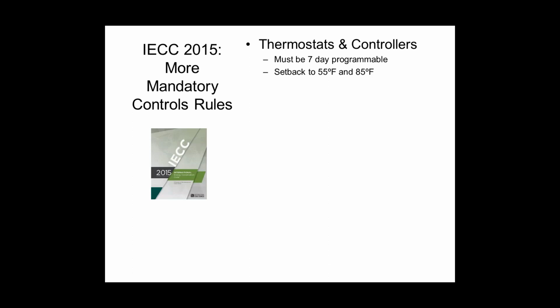You have to have the ability to set it back to 55 and 85 degrees. If the occupant chooses to change that later, that's fine, but you as the specifier or installer need to provide them that stat and set their setbacks for those numbers, and then whatever they do later on, that's their own thing. You have to have at least a 5-degree dead band.